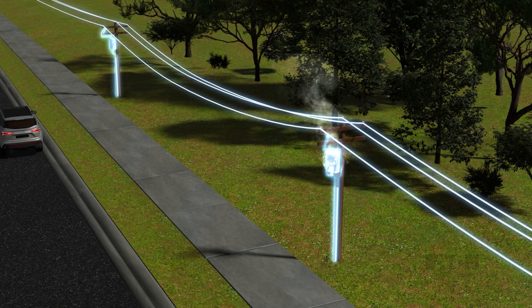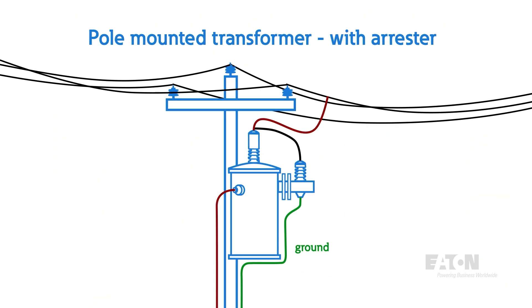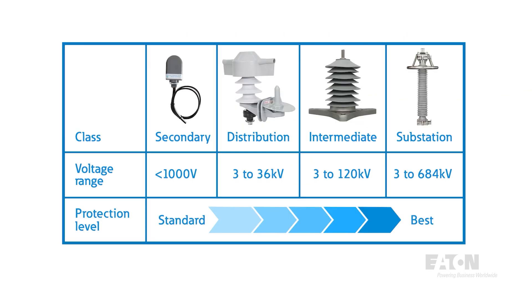These extremely high voltages can propagate through power lines and damage equipment. However, surge arrestors can be placed right next to equipment to help filter out these transient overvoltage conditions. There are four different classes of arrestors dictated by IEEE: secondary, distribution, intermediate, and substation. This just determines the range of voltage ratings as well as the protection level.